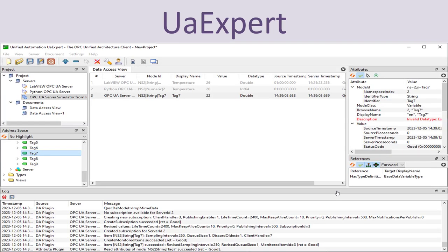Here you see the UAexpert OPC UA client in action. In this window you add servers and connect to OPC UA servers. When you select one of those you will get the list of available tags for that specific server, and then you can drag one or more tags into this window in order to see the current state of that specific tag. Here you can see the value, the name of the tags, node IDs, name of the server, timestamp, etc.